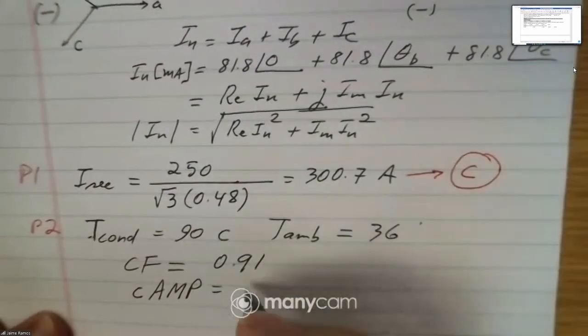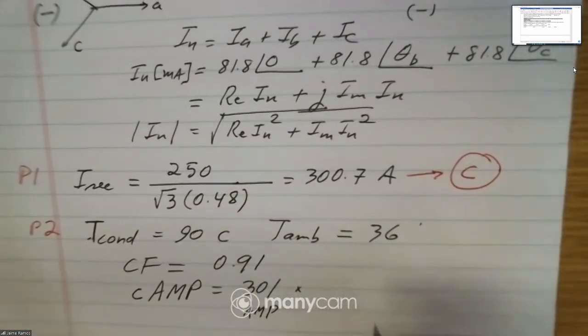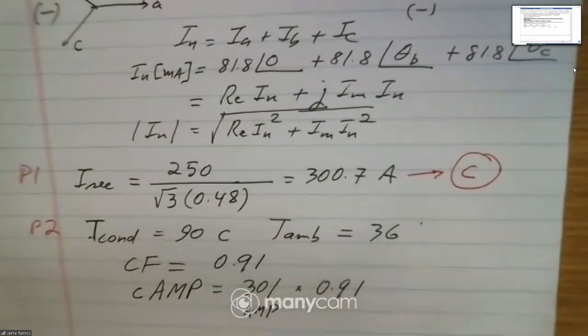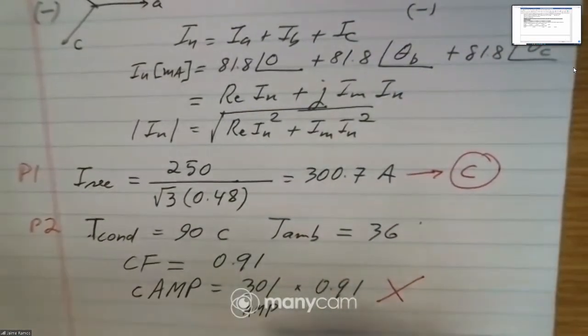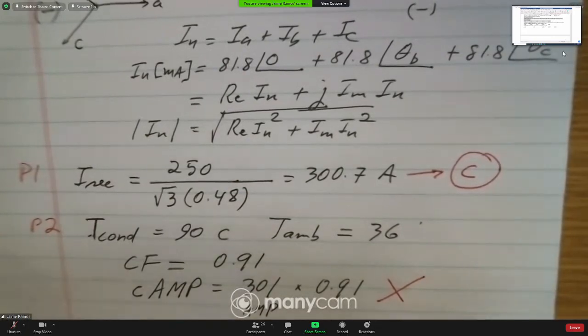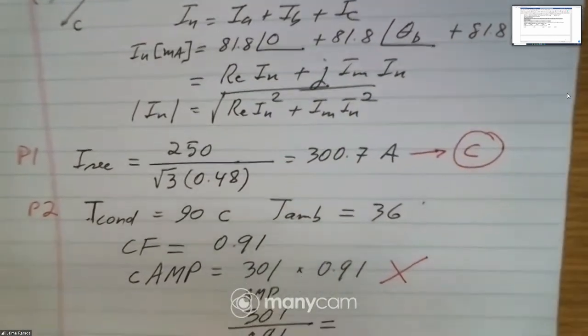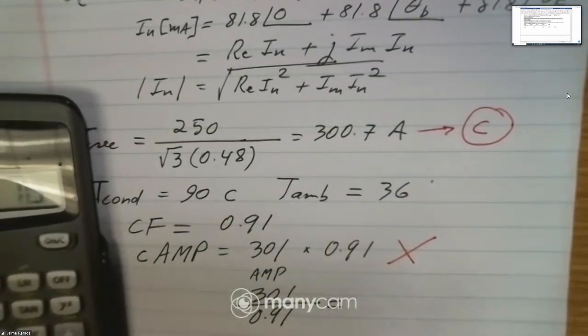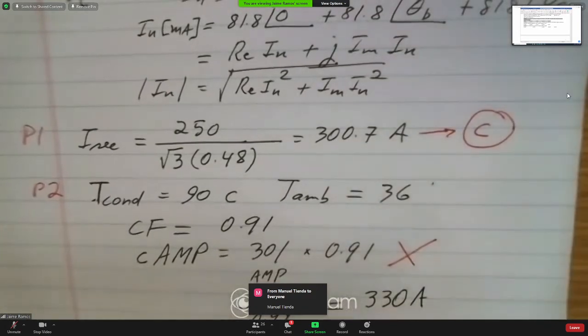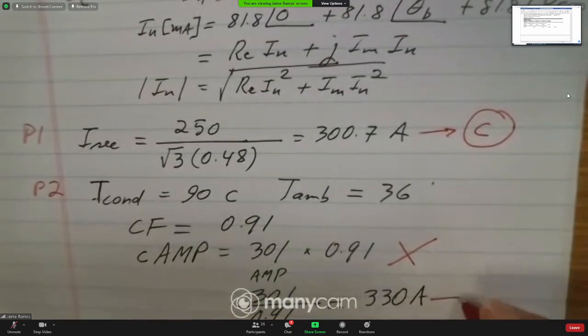So then the corrected ampacity is equal to 301. This is the ampacity that we determined, times, times or divided by. No, I think we must not multiply. We must divide. Okay, so the ampacity, so then instead of multiplying by the correction factor like that, divide by 0.91, 330 amp. So therefore that is A.